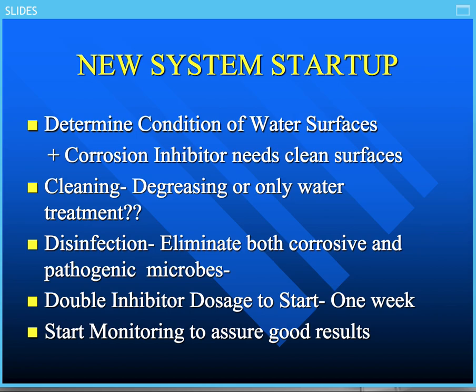It probably wouldn't give you the scaling tendency, but on the other hand, it could mean that you do have some biological contamination. But the key here is to start your monitoring so you can determine what results are actually starting up right now with a new system. Don't wait for, say, a month or 2 months or 6 months and then start your monitoring. That's too late. Any of the corrosion problems and any of the bio problems could have started already, and that would give you the trouble. So keep that in mind for starting up a first-rate cooling water treatment program.